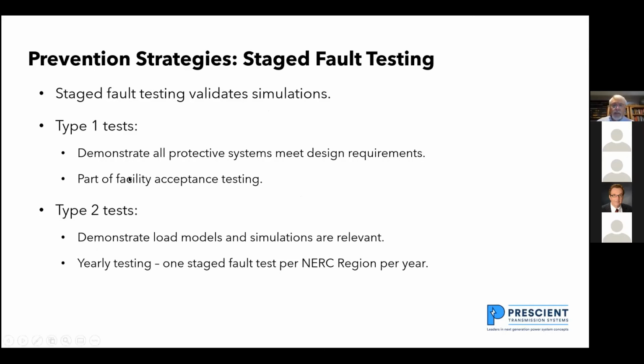We should be demonstrating that all our protective relaying systems that we put in for the system meet their design requirements by doing a staged fault test as part of all new facilities that are energized. And in addition to that, we should be doing type testing. Type 2 tests are demonstrating that our load models and our simulations are relevant.